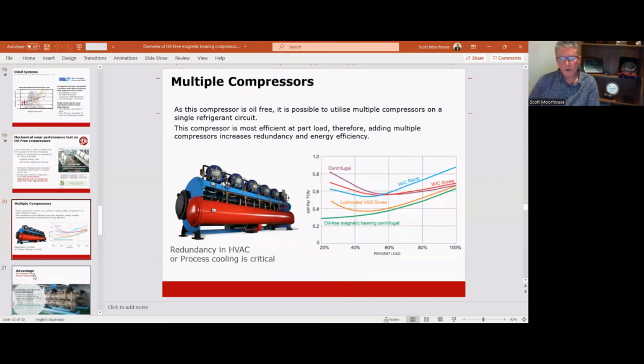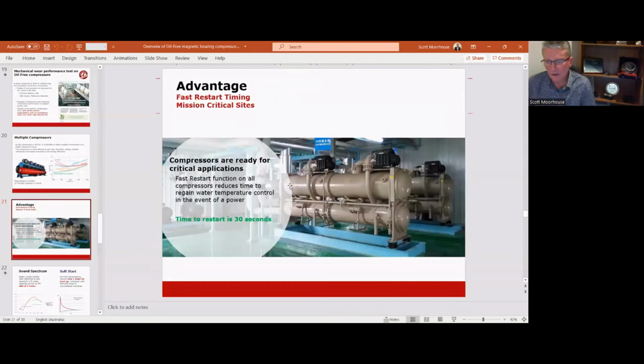Also, with smaller high-speed machines, a lot of applications are using multiple compressors. So this is a key in redundancy for certain applications. And it also means we can unload the compressor significantly more than a large single compressor machine. So we have a big advantage with multiple compressors. Also, when we levitate a shaft and run it, we're not generating any massive amounts of heat into the system. So we can get our compressors off and running in 30 seconds if we have a power outage. This is a key advantage in mission critical sites such as data centers.